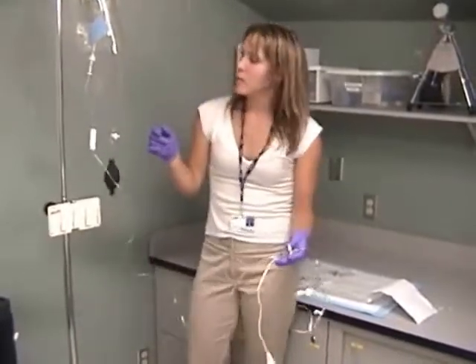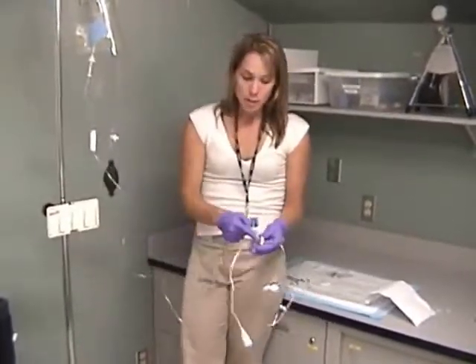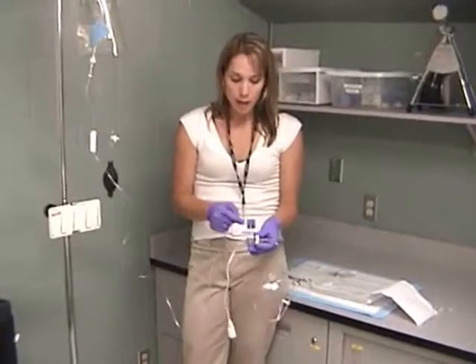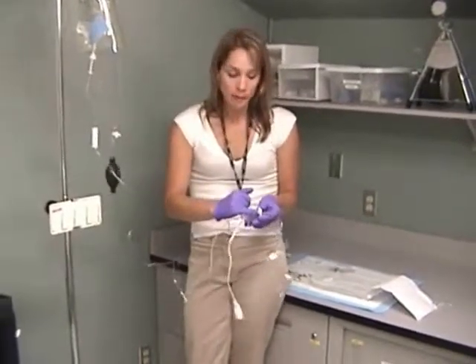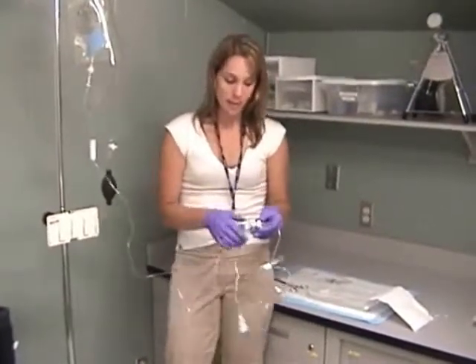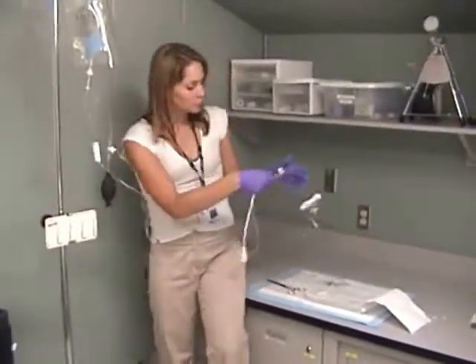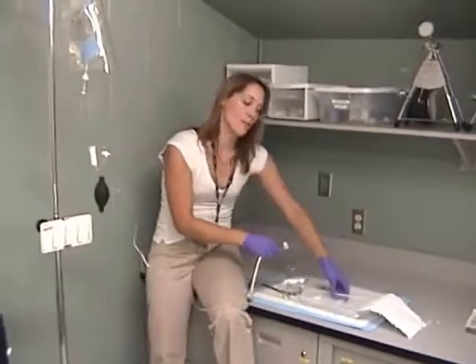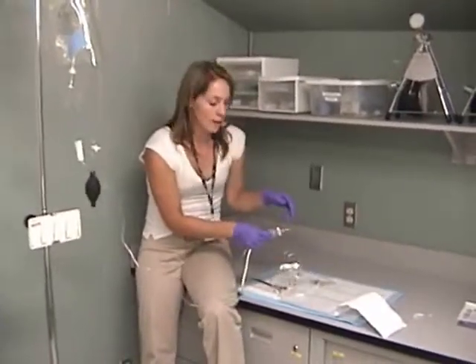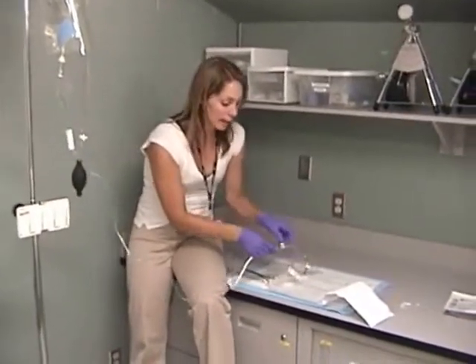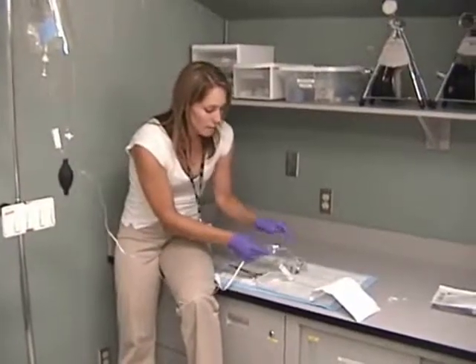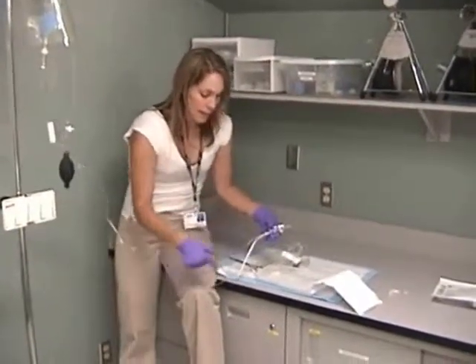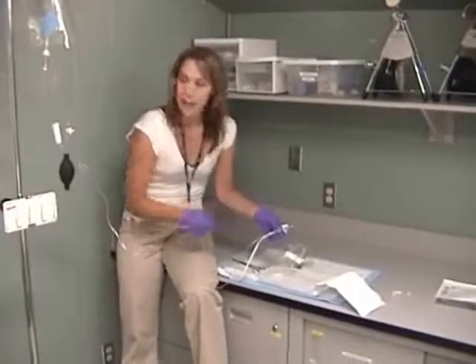Now we can start to flush the system. So this first section we're going to flush is down to that first stopcock. It has a white cap on it with a little hole in the end, and that's going to let fluid actually come out of it while maintaining the sterile sample port there. I tend to flush into the container I took it out of, but you can also flush it over a garbage can. So you can turn your stopcock off to this end of the system, and now when I flush, the fluid is going to run out that way.